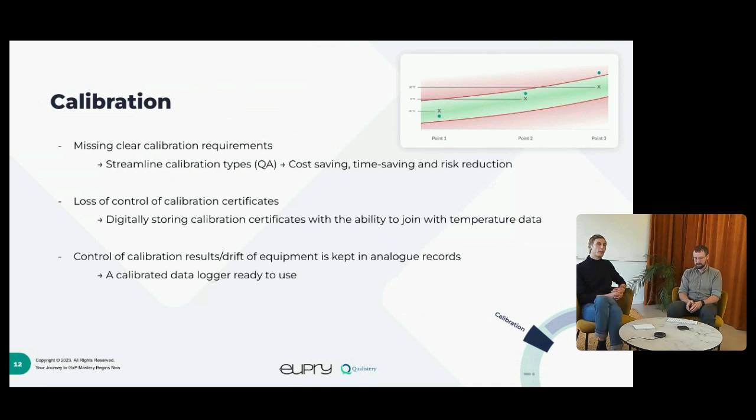It might be a bit of a funny point to pull in front of you guys, because I think this is the way it's normally done. You have a calibration provider and they're running a lab and testing your equipment, and then they send you back the equipment, and then you realize at arrival that, oh my God, it didn't actually go through. But if you can really try to rethink that process, because you can save so much time. It might just be 10%, maybe even 5% of all your calibrations, where you end up getting in return a device or equipment that has not passed.